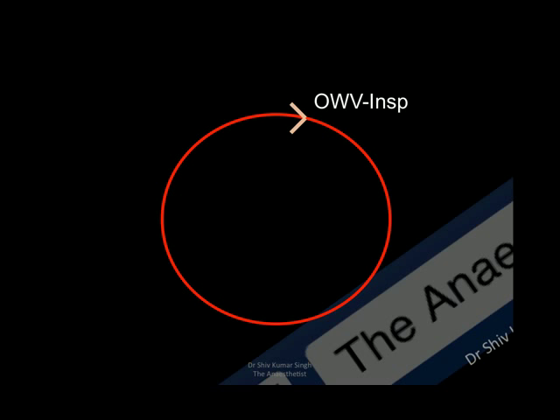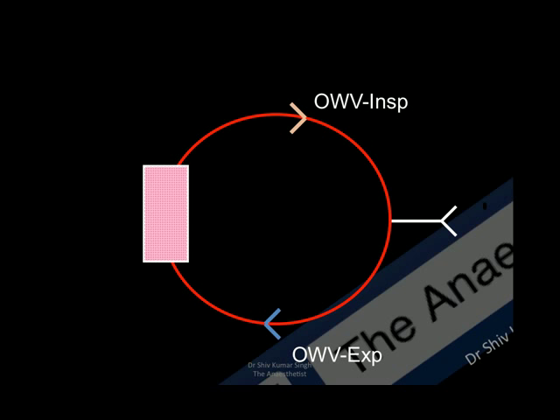If you look at the circle system, a circle system is a circle with one-way valves — an inspiratory limb and an expiratory limb. The gases will flow from the machine to the patient on the inspiratory limb, and from the patient to the soda lime on the expiratory limb. It is obviously attached to the patient, and the most important component of the circle system is the soda lime.